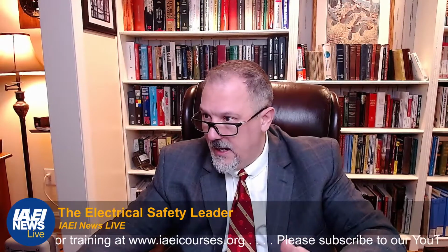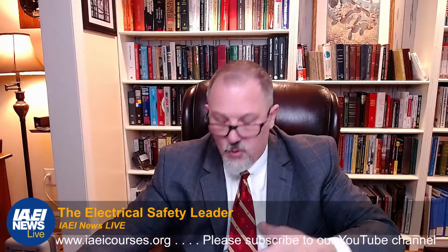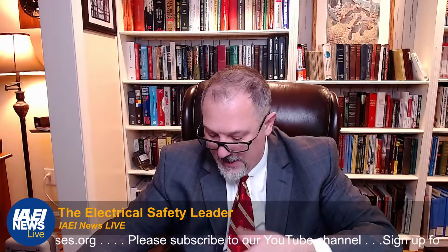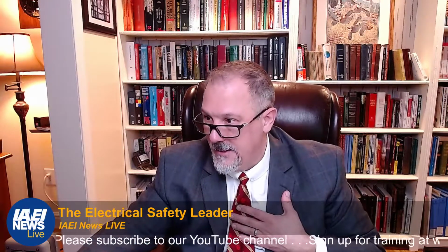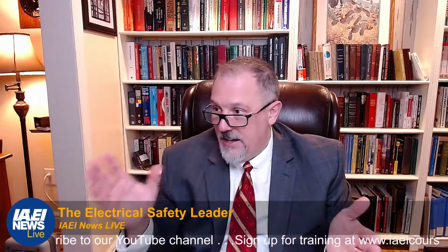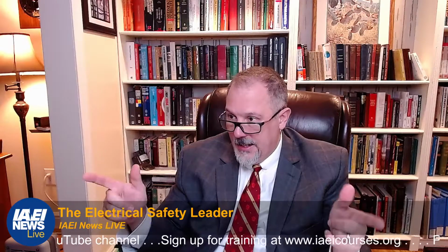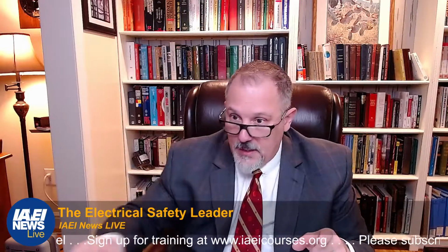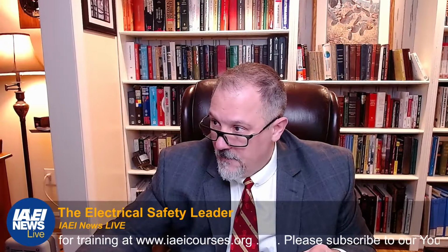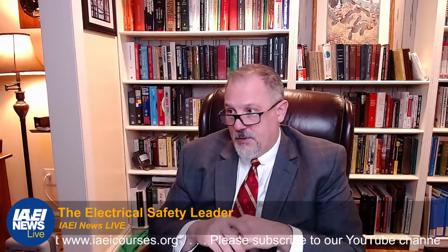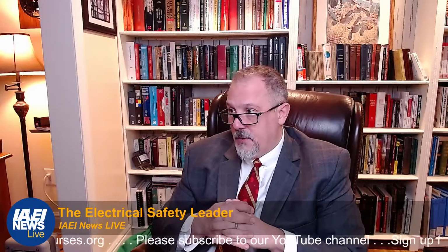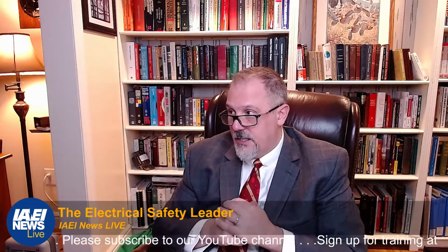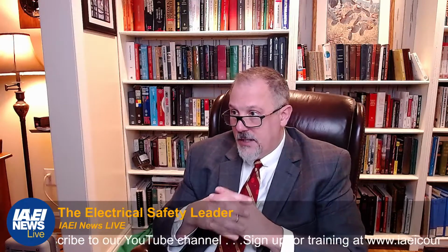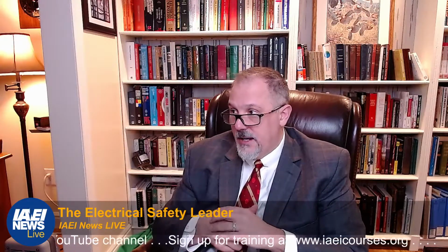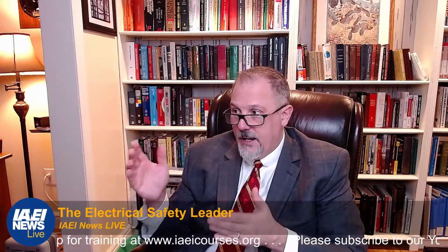They incorporated the infeasibility sections. They incorporated the equipment operating less than 50 volts. They incorporated the normal operating condition. But in my opinion, they lost what a normal operation condition is that is used later. Check that one out, please. I think that's a concern. Another thing they did, they gave an exception. An energized disconnecting means or isolating element shall be permitted to be operated to achieve an electrically safe work condition or to return equipment to service that has been placed in an electrically safe work condition. The equipment supplying the disconnecting means or isolating equipment shall not be required to be placed in an electrically safe work condition provided a risk assessment is performed.